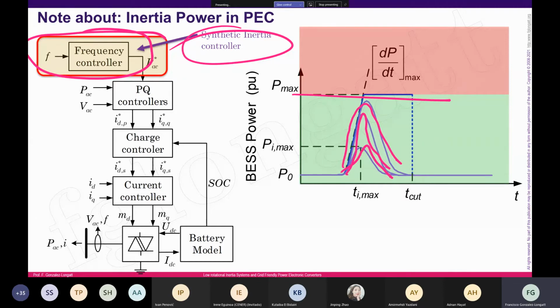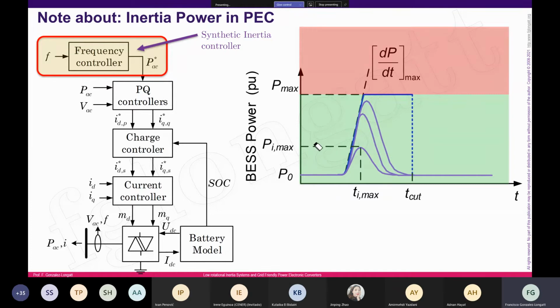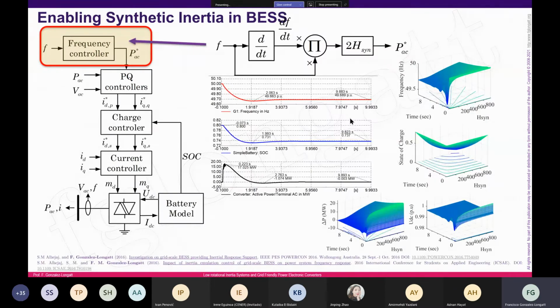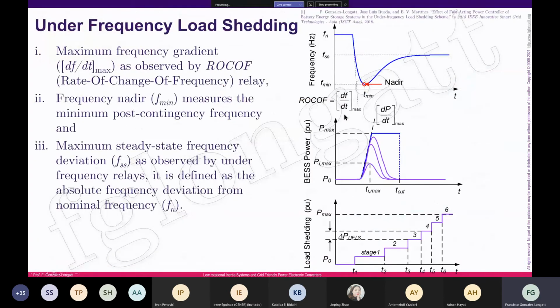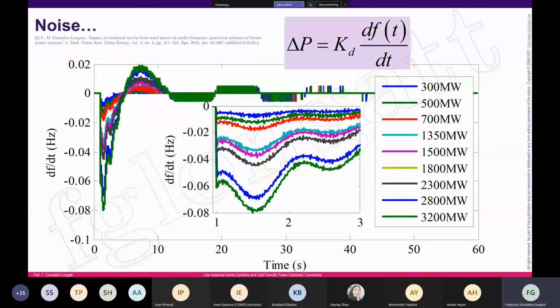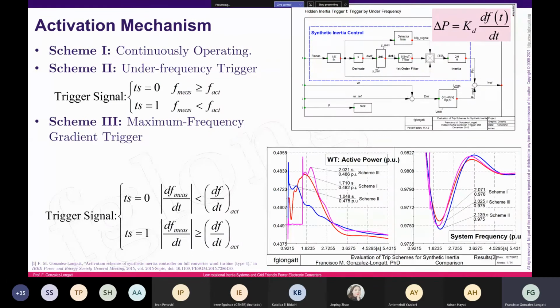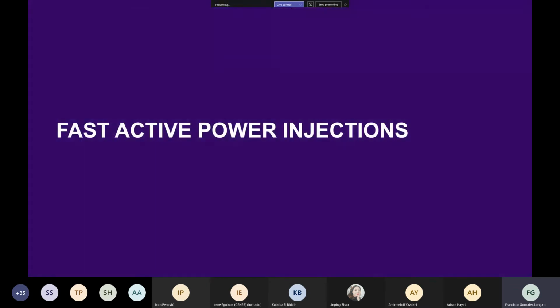Okay, we have done many simulations. We have been using batteries. We use batteries to emulate inertia, and we use the inertia in order to avoid under-frequency load shedding. But one of the complaints that I have about inertial response is that you need to use the ROCOF. And the ROCOF of a frequency signal is typically a very noisy signal. And that very noisy signal creates another problem, and that is the activation mechanism that we will use to activate the controller. And that is the reason that in recent times we proposed the concept of fast active power injection.